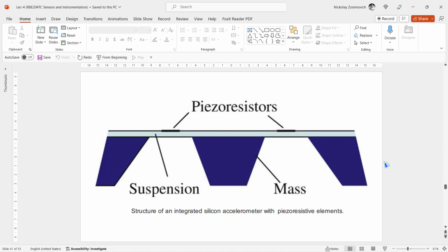The springs are silicon beams made from the epitaxial layer by etching holes in the membrane, and the mass is suspended from the substrate by the thin beam, on top of which the piezoresistive elements are deposited. When the structure experiences an acceleration in a direction perpendicular to the chip surface, the mass will move up or down due to its inertia. The beam bends and the piezoresistive elements respond to this deformation. Since the device is sensitive to inertial forces, it can be packed in a hermetically closed housing, making it resistant against mechanical and chemical influences from the environment.